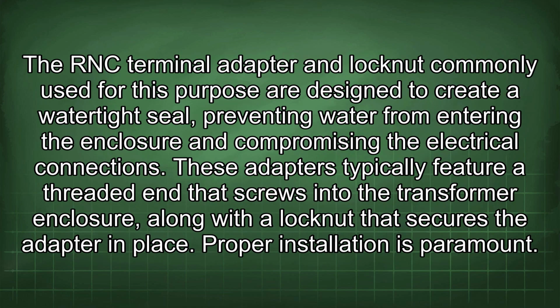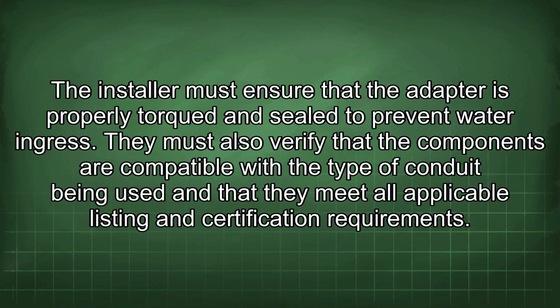The RNC terminal adapter and lock nut commonly used for this purpose are designed to create a watertight seal, preventing water from entering the enclosure and compromising the electrical connections. These adapters typically feature a threaded end that screws into the transformer enclosure, along with a lock nut that secures the adapter in place. Proper installation is paramount. The installer must ensure that the adapter is properly torqued and sealed to prevent water ingress. They must also verify that the components are compatible with the type of conduit being used and that they meet all applicable listing and certification requirements.